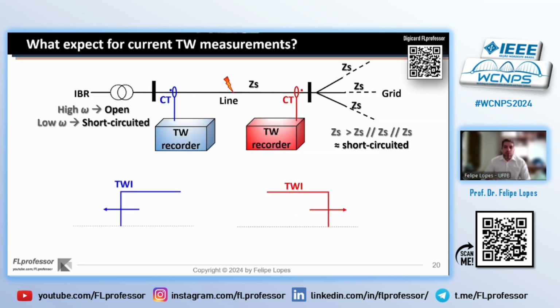And just to explain why it can be a problem, let's consider here a transmission line which interconnects an IBR. If we consider only the transformer here, for higher frequencies it will behave as an open circuit, but for low frequencies it will behave as a short-circuited path. And if the fault launches traveling waves, and I am here talking about current traveling waves because most of the existing protections based on traveling waves are based on current traveling waves.